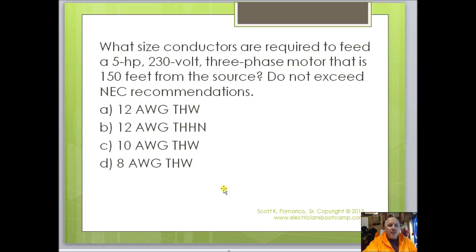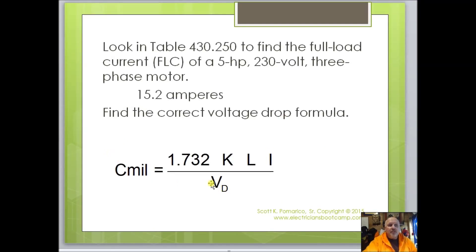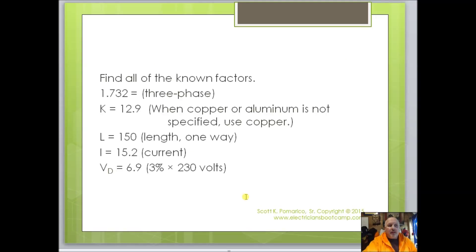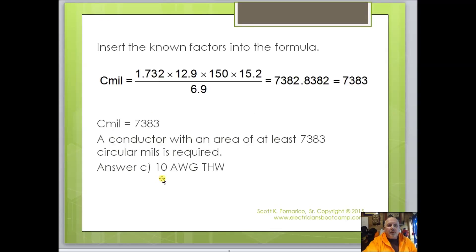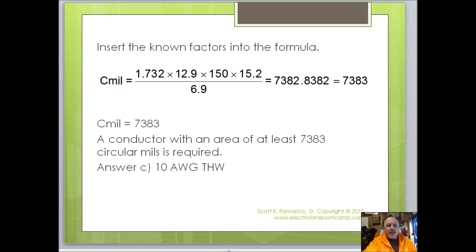Another example — a feeder: 5-horsepower, 230-volt, 150 feet away. Do not exceed the NEC recommendations. Using table 430.250, I found 15.2 amps. Plugging into the circular mils formula with all that information, I found that number 10 wire is required. This is another example of a voltage drop problem you might see on the test.